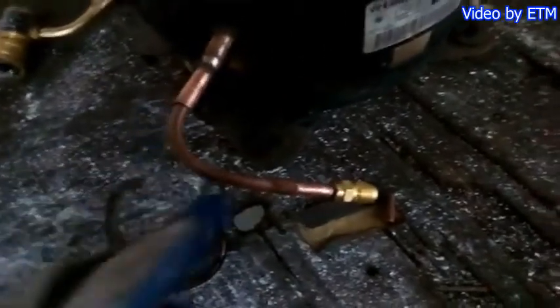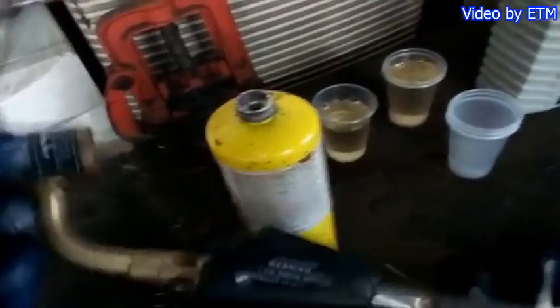We cut it, then inserted a new section, and bent it using a tube bender. We also used a stubby or mini tube cutter. We also used pliers. The tube bender bent it properly. Then we soldered it using MAPP gas and a MAPP gas head torch. Now it has a proper connection for the new oil.